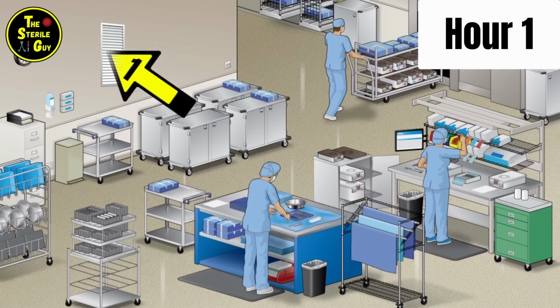Now in the clean areas, it is the exact opposite. More air is supplied to the room and less air is pulled out of the room. This creates what is called a positive pressure situation. Instead of these areas sucking air from around the doors to the inside of the room like decontamination does, the clean area actually pushes more air out through those cracks to the rooms outside of the clean area.